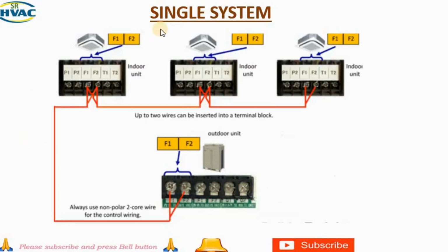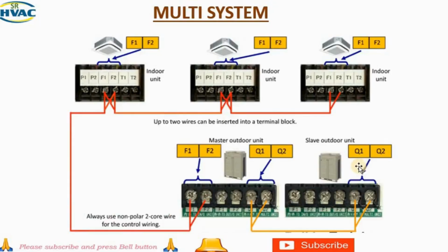You can see this is the single system. This is how looping is done. 1, 2, 3. Then it is going to the single outdoor unit. If it is single, it will connect to F2. Okay, here if it is a master and slave multi-unit, it will be connected here. Okay, we will see that also friends. You can see this one is our slave. This is the master unit. This is connected. You can see always use non-polar 2-core wire for the control wiring. It is connected to the F2. Okay, 2 wires can be inserted into the terminal.